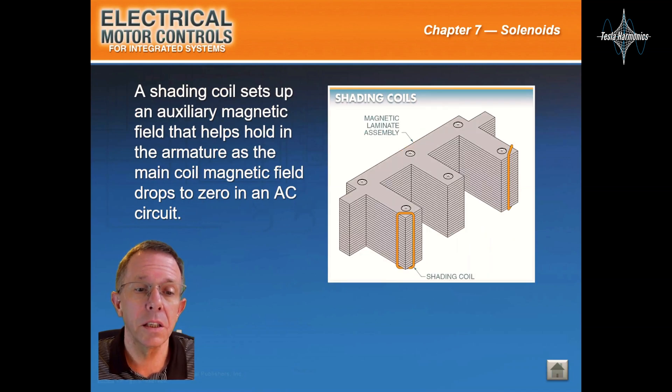A shading coil sets up an auxiliary magnetic field that helps hold in the armature as the main coil magnetic field drops to zero in an AC circuit.